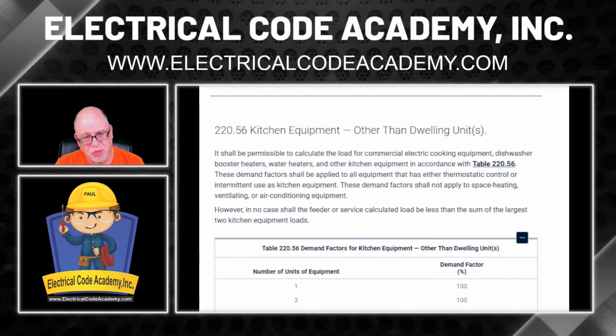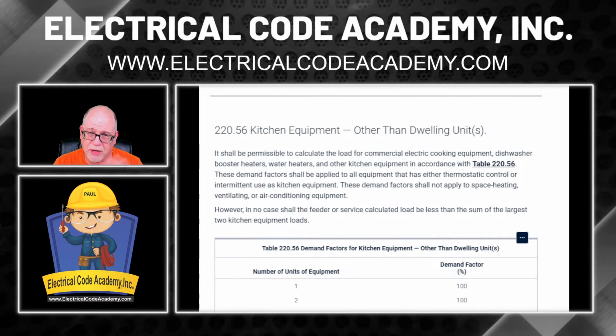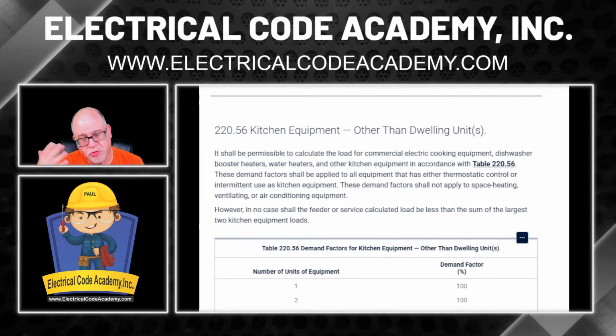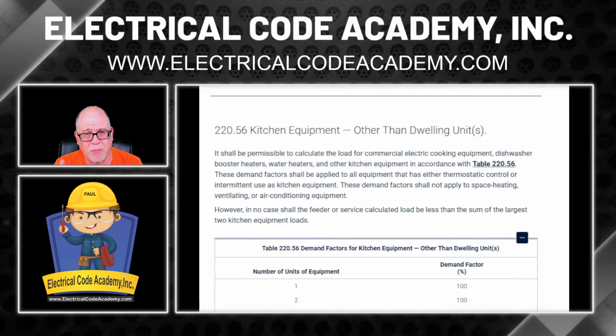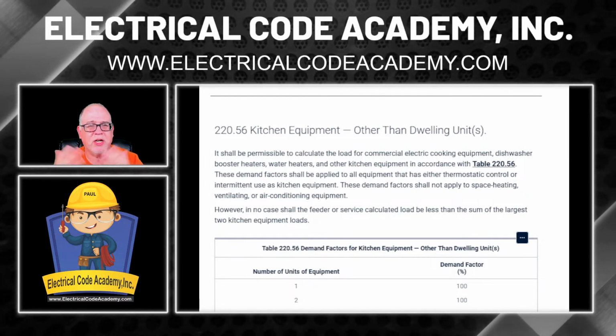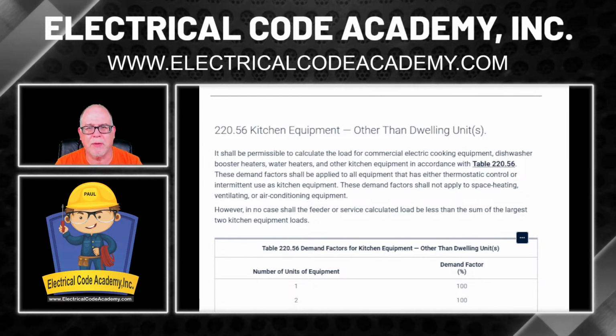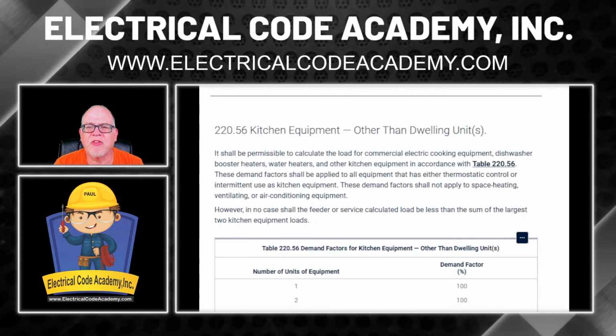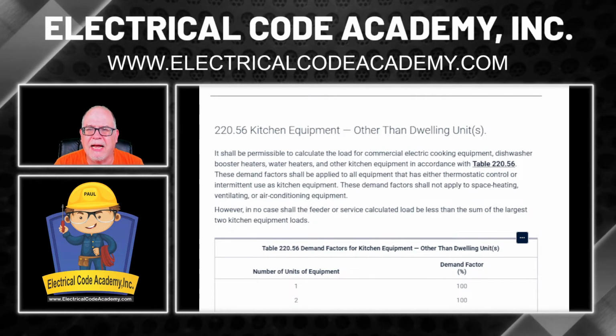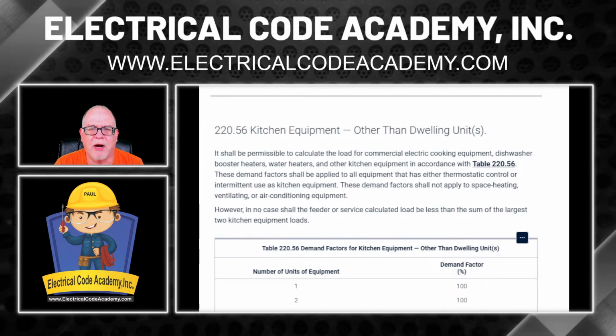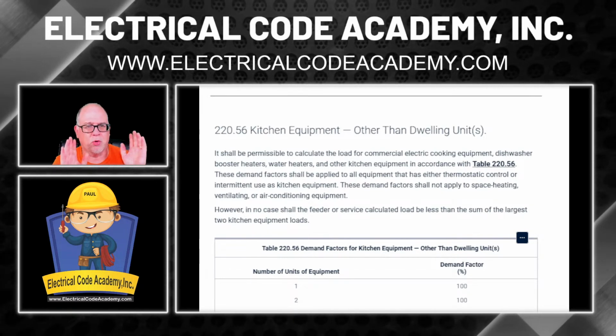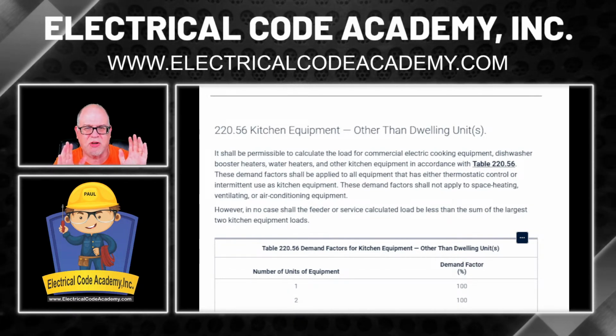Well, obviously, disposal's on when you need it. Water heater is going to come on when it's needed. Booster heater is going to come on when it's needed, but that's also probably thermostatically controlled. So we're good with all these pieces of equipment. It also says these demand factors shall not apply to space heating, ventilating, or air conditioning equipment. Yeah, because we've got our own rules for that. So we're not going to have anything to do with that.